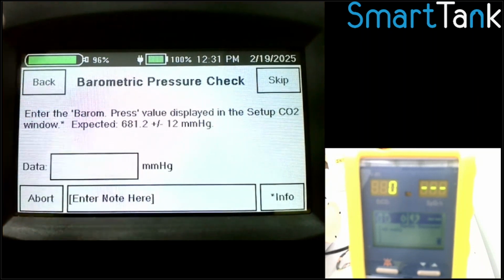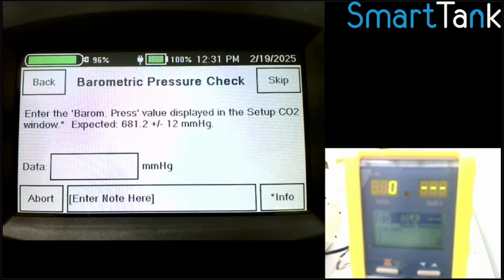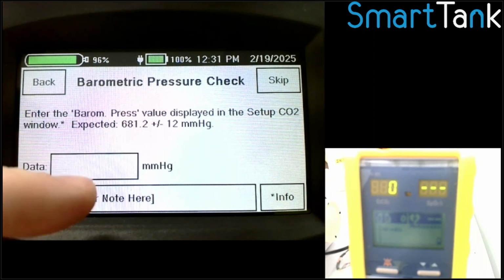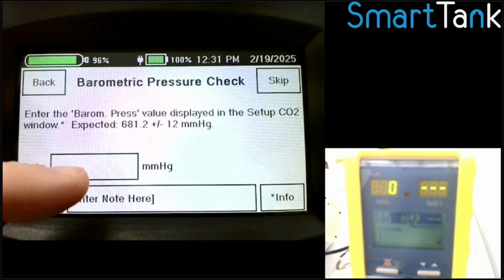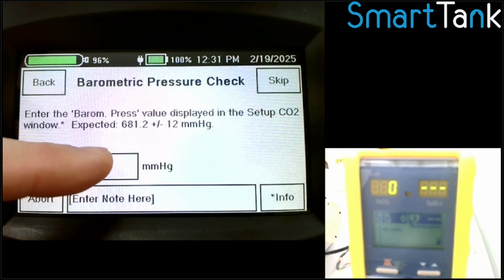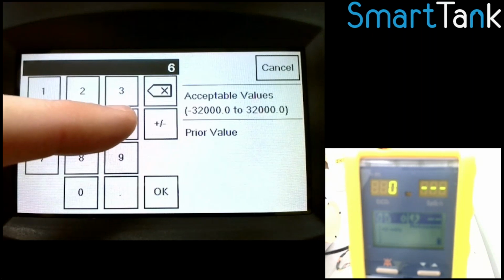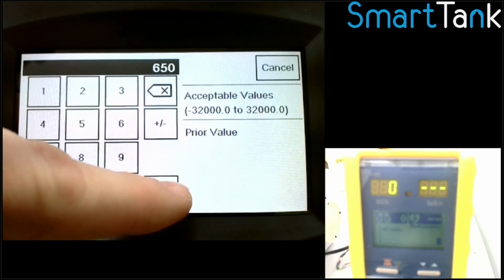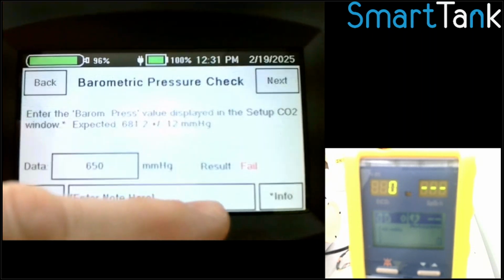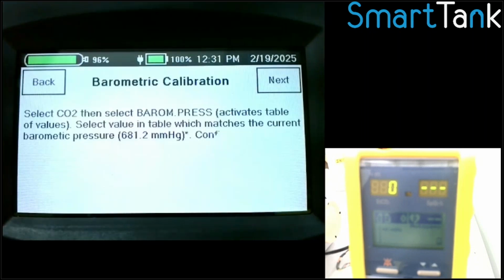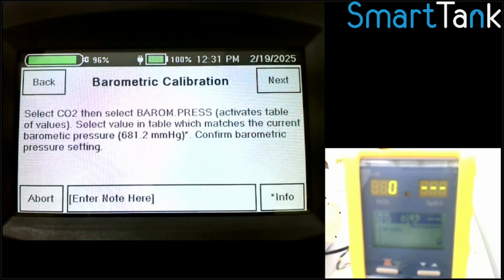Well, that 681 comes from a barometric pressure sensor that's inside the SmartTank. And so it knows what it should be. And so you can use that as a reference or a check. Now, to help you understand sequences, I'm going to show you what happens when you fail it. So if I enter this as 650, let's say, you'll notice it fails. And now I hit next, and the sequence is smart enough to say, hey, you failed that.